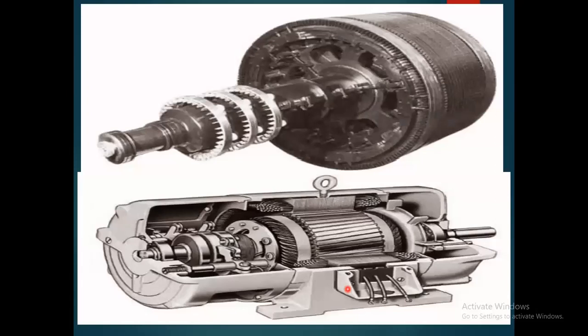This is the main structure you can see of a slip ring three-phase induction motor. The slip ring induction motor is also called a wound rotor induction motor. On the rotor side, these are the particular windings of the rotor that are connected with the rings, and on the rings the carbon brushes rub continuously to control the speed of the rotor, particularly when we need it.